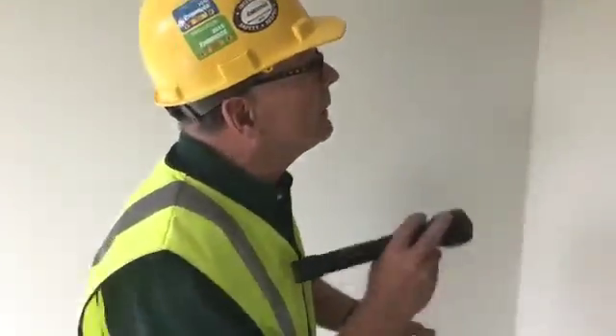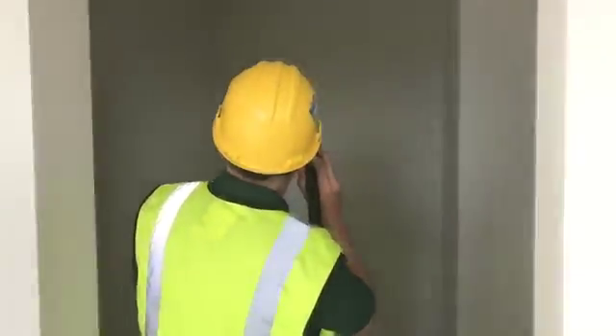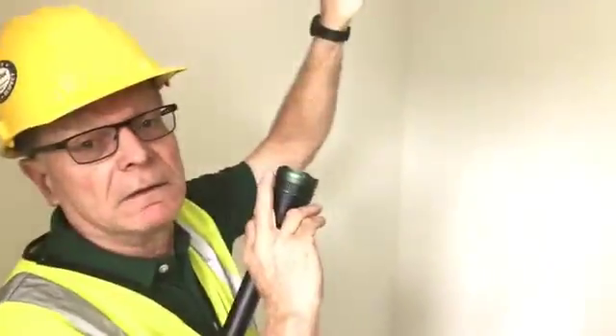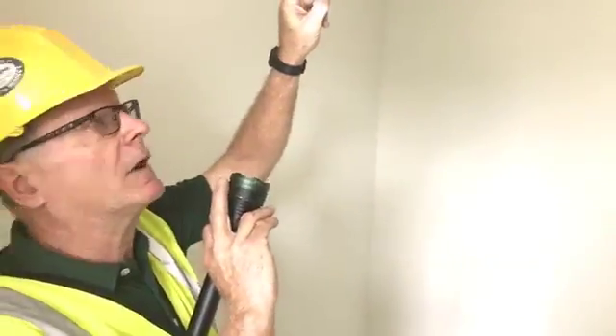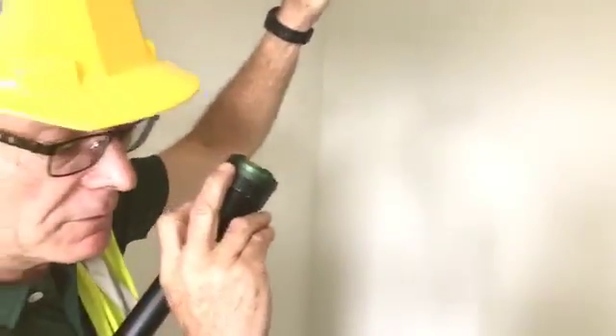Over here for the test, and this reflects throughout construction, they've gone ahead and we've sealed these back up so that we're not getting any paint, dust, drywall spray into the exhaust fan. This would definitely be a problem at final. You can see the drop here is not air sealed. This is a sprinkler drop, and we cannot disturb that opening that comes through the drywall per our fire code.